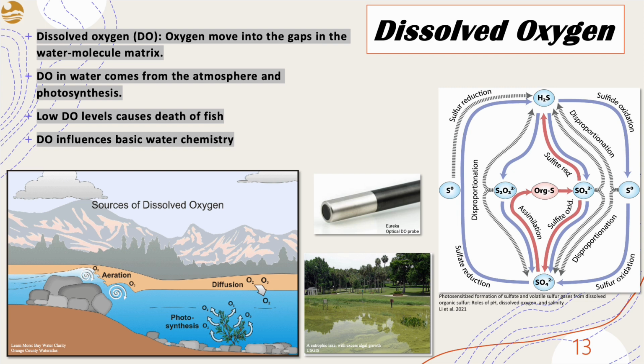The type of dissolved oxygen sensor we have on our data sonde is an optical dissolved oxygen sensor. The blue light from the sensor causes the oxygen active compound to fluoresce. They absorb energy in the form of blue light and then emit energy as red light. So the emission of red light is reduced if oxygen molecules are present in the interface of the oxygen active compound. The more oxygen present, the smaller amount of red light will be produced.